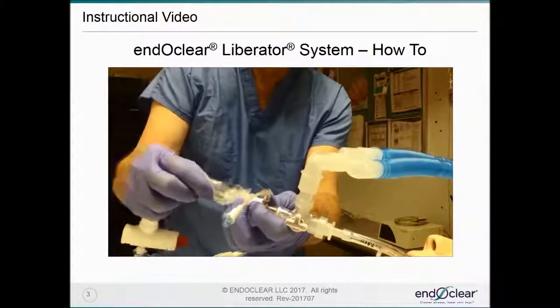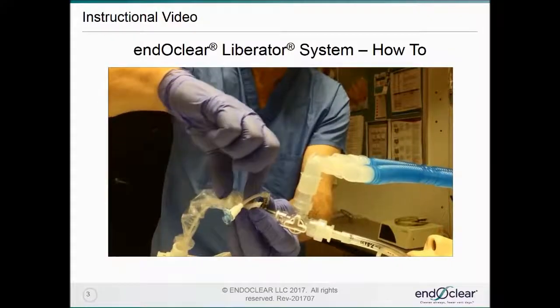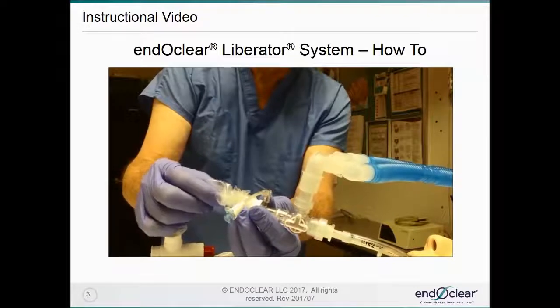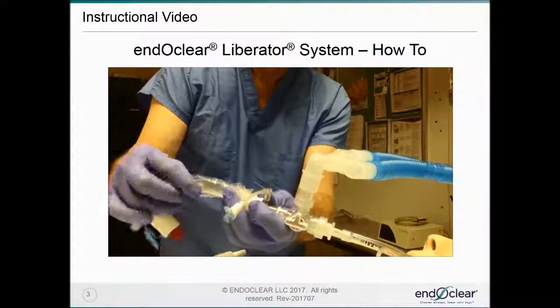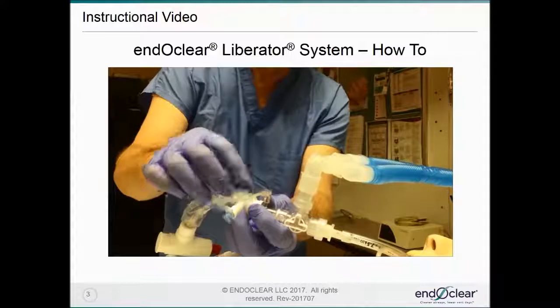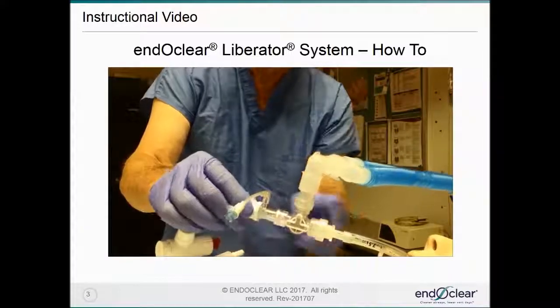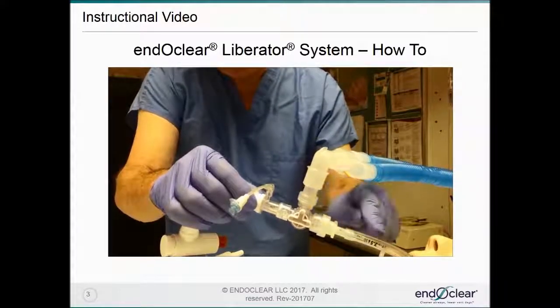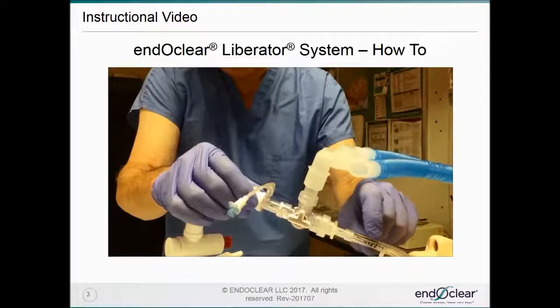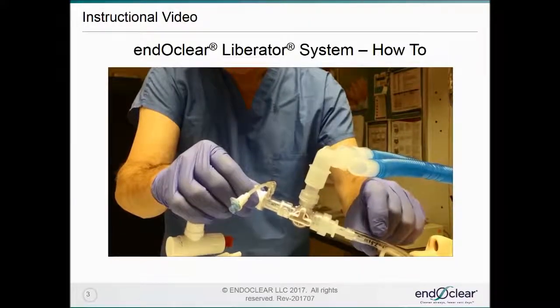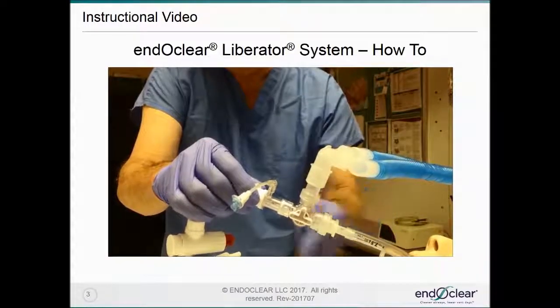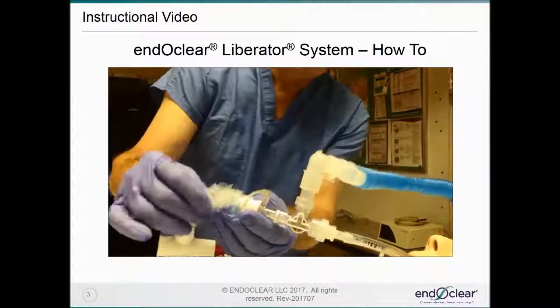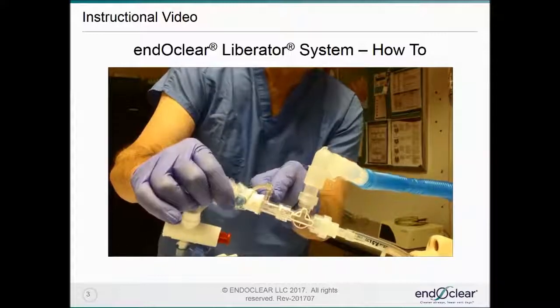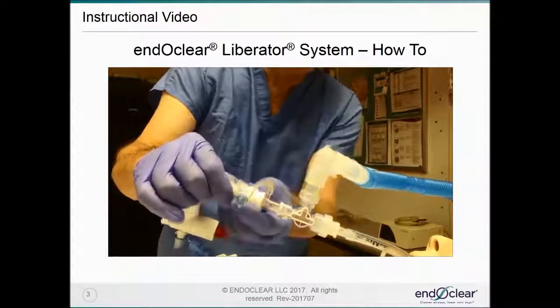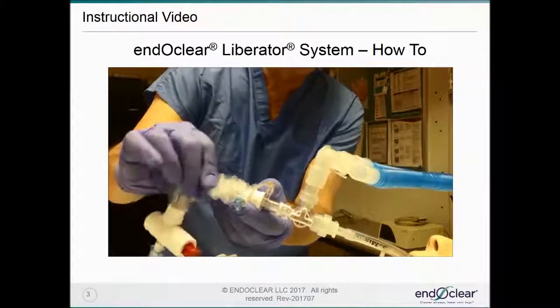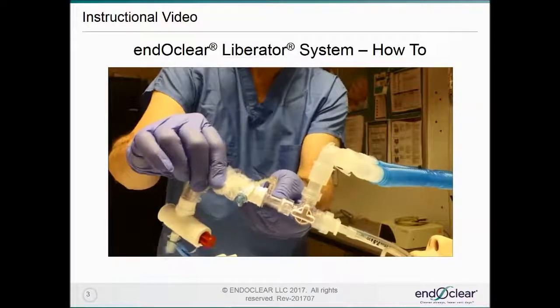the sheath onto this area, which is a small plastic tube, and you can gather the sheath as you advance. The initial time the Liberator is used, the centimeter markings are lined up with those on the endotracheal tube. And once those are lined up, we know that the wiper is positioned appropriately. At that time, we also look in the cleaning garage window and are able to see a centimeter marking, which in this case says 38.